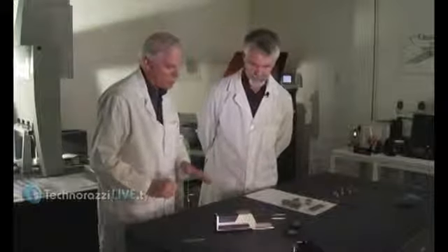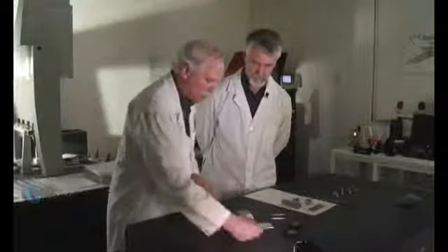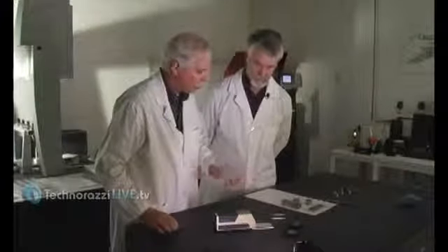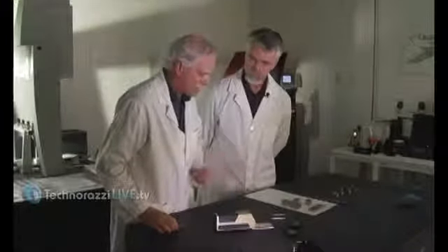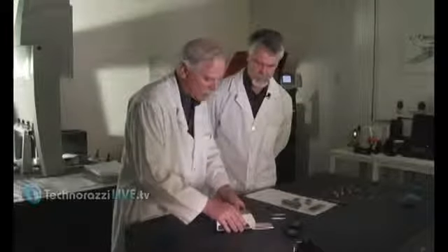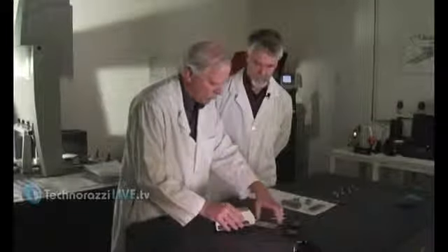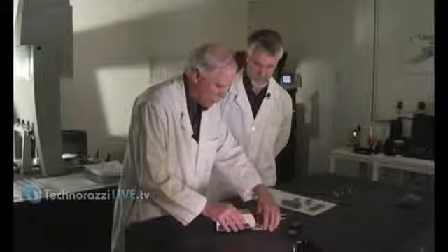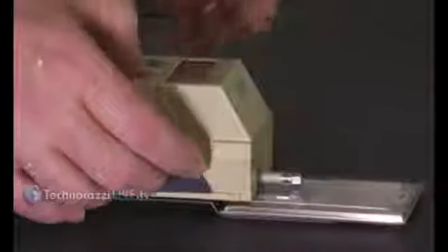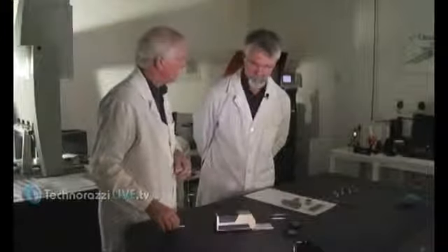Okay. In a calibration lab, what happens is this stylus will typically wear. That is the part, other than physically damaging the unit, the only part that really wears out is the stylus. As it rubs and rubs and rubs, it eventually loses some of its shape. So we will check the stylus with the other patch, with the finer patch. This one happens to be 15 microinch. As the stylus wears, they typically will read a lower number. They're typically flattening out some. And there is a limit to what they're allowed to wear to before they need to be replaced.